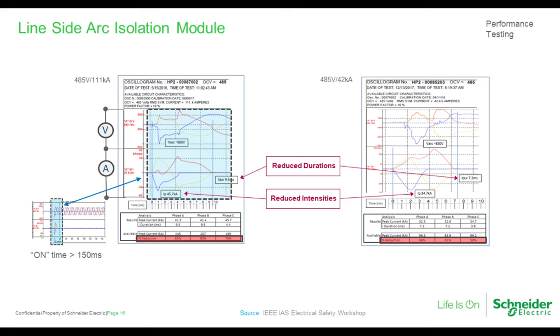So these are oscilloscope traces of actual test results on MCC ArcBlok. Not everyone is used to looking at these, so let's take a few seconds to discuss what they are. The traces contain voltage and current measurements taken during the arc flash testing in the lab. The vertical scales are voltage and current, and the horizontal scale is time. In terms of scale, the upper traces are on the order of plus or minus 1,000 volts. The lower traces are on the order of plus or minus 60,000 amps. And the time scale is on the order of 10/1000 of a second and represents only a portion of the test for which there was arcing. More on this in a bit.